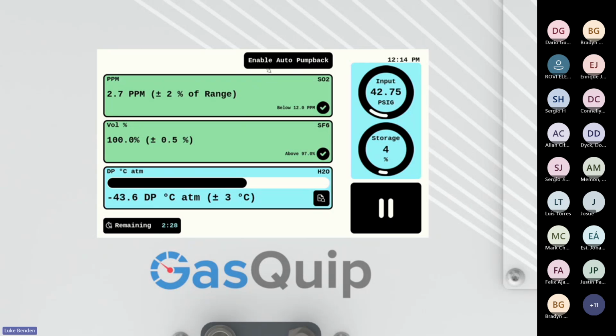Didn't talk about this yet. So this enable auto pump back is a feature that, if you click it to enable, and we just enabled that, it'll run in the background. And by run, I mean the pump back will pump the gas that it just tested, or anything else that's stored inside the device, back out through the sample hose port to the breaker that you're testing, in the background as you look through the results.